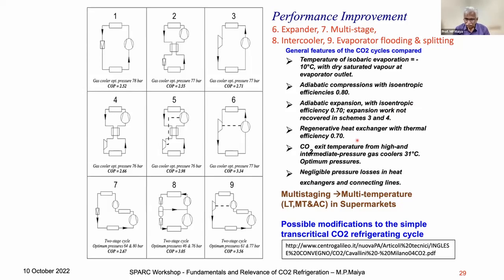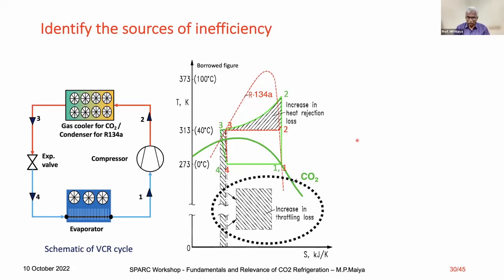Now, you see, we can't use the expander because we're still in the developing stage. The expander is not available in the market. So what should be done? Okay. The expander is not possible. We know what the inefficiencies in the system are. You have to identify them. One is the throttling loss. Of course, we talked about the expander, where the throttling loss will not be there, but it is very difficult to use the expander. Not possible.